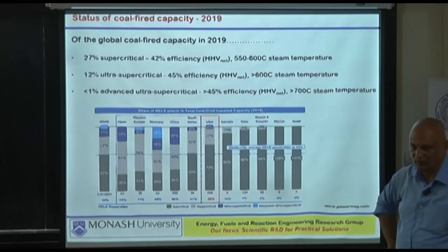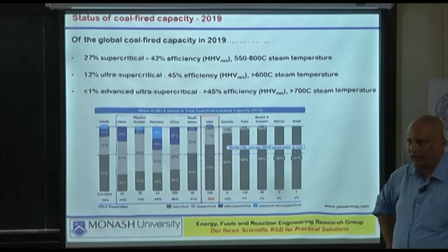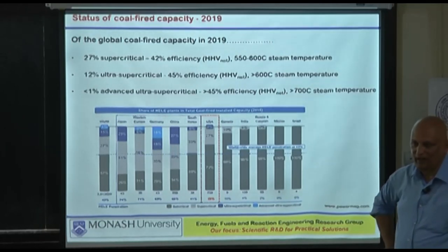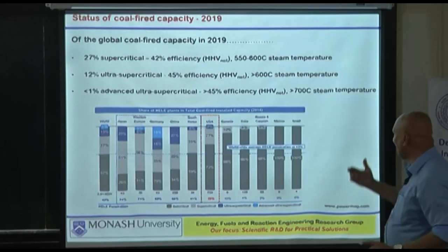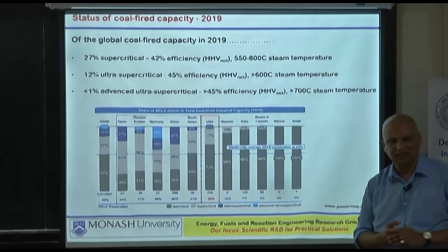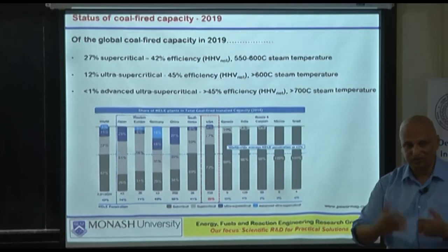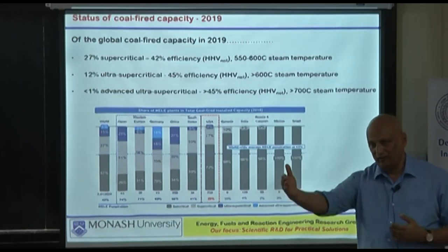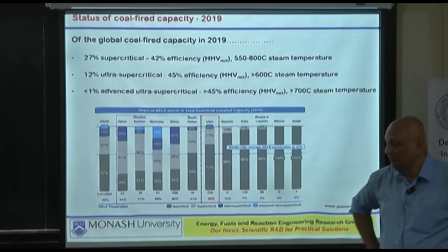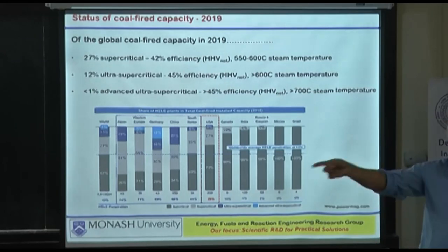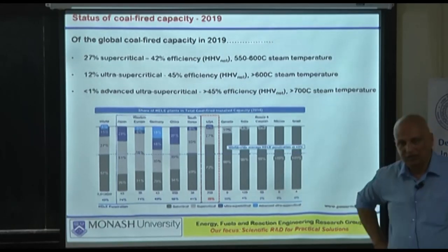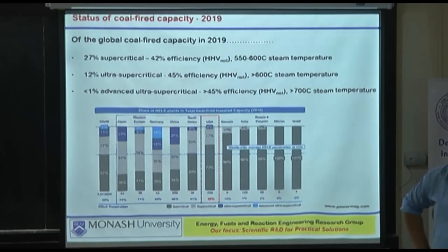It depends on what type of boiler feed pump you have. For ultra supercritical, no one has gone beyond 280 bar at this point in time, because the very high pressure and very high temperature have significant implications on the metals, the composition of the metals, and of the tubes and their longevity. One of the problems in steam tubes, post boiler into the turbine and then right to the condenser and back to the boiler again through the feed water section, is that as you increase pressure and temperature of the steam, you have to maintain a very low level of oxygen in the steam.